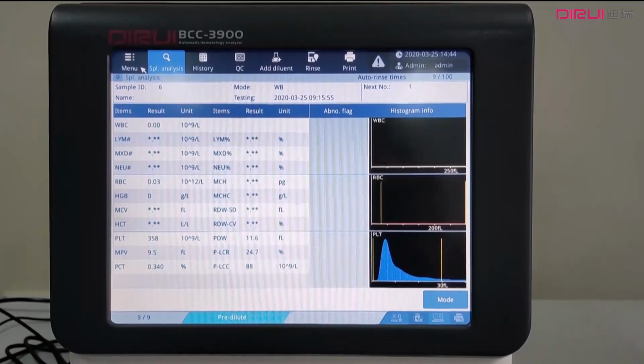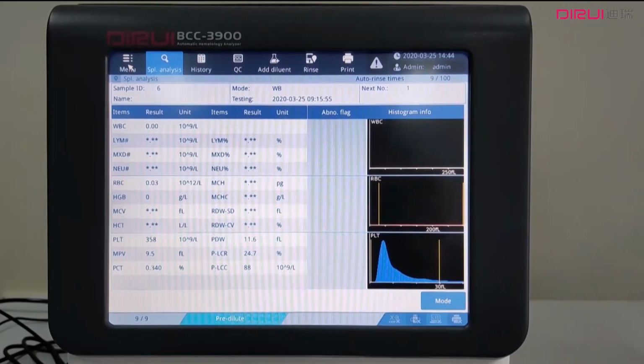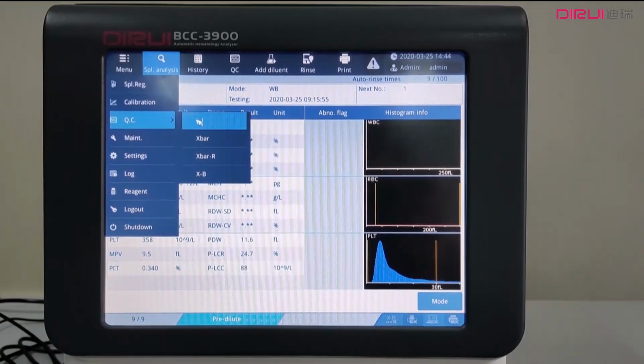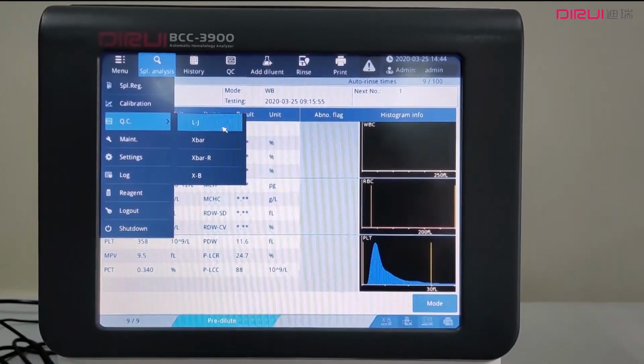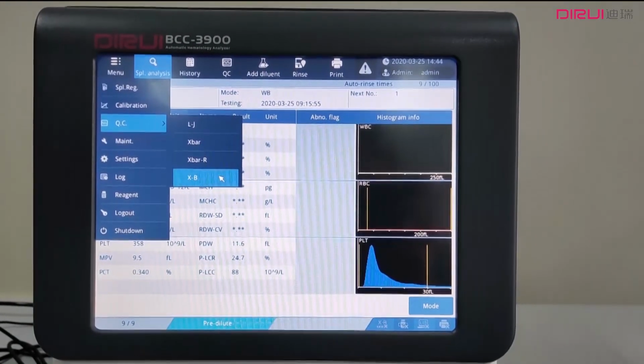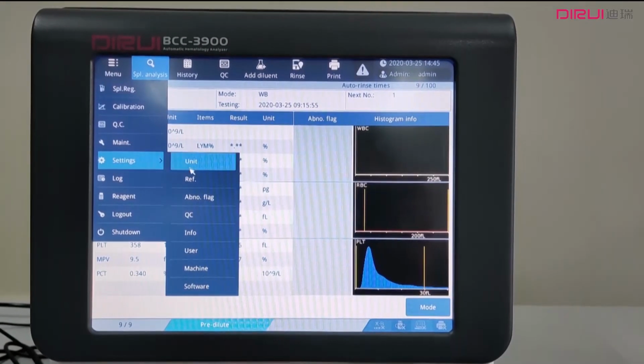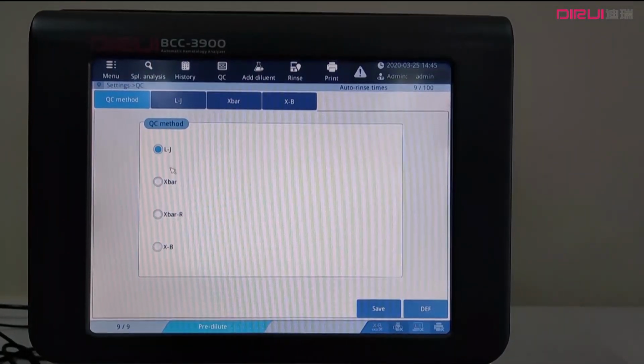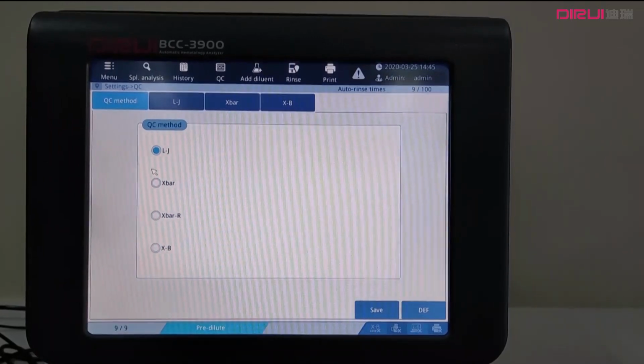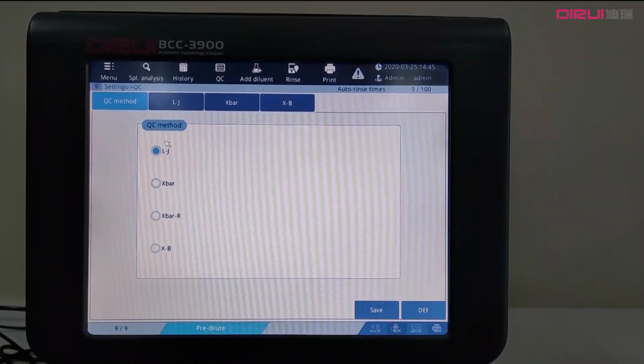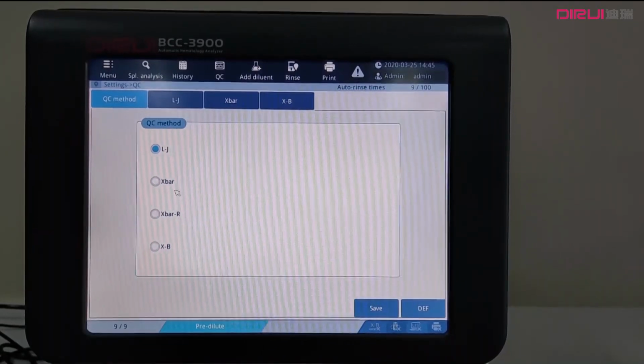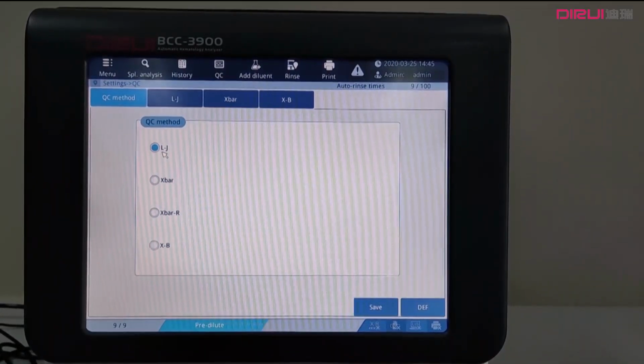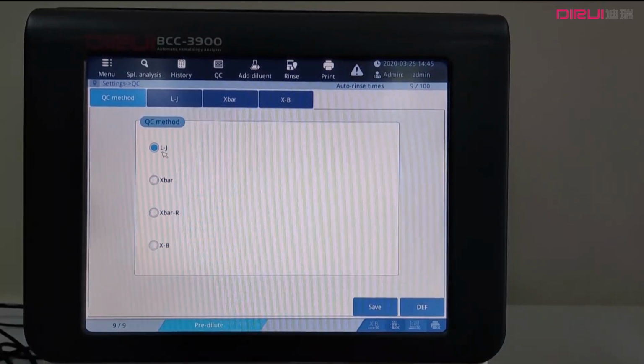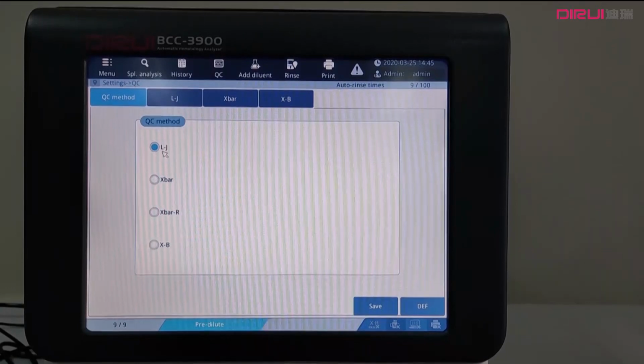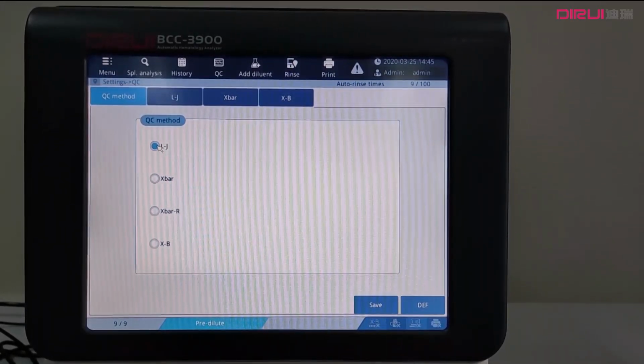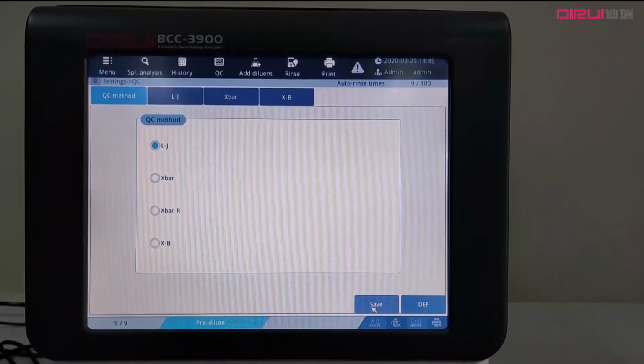Before we conduct the quality control, we need to input some settings first. So go to menu and QC. Now you can see there are different methods: LJ, X bar R and XB. The same functions you can go to setting and QC, and you can see the same functions here. In our machine, the first 3 are the most commonly used methods, and out of these 3, LJ is the most commonly used. It is also known as Levey-Jennings or average QC. So we will select this one and press save.